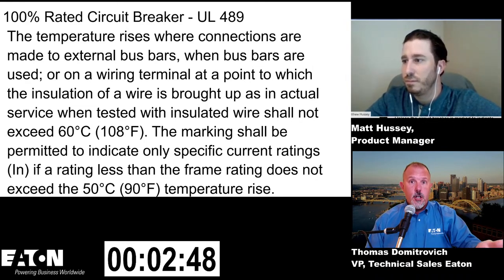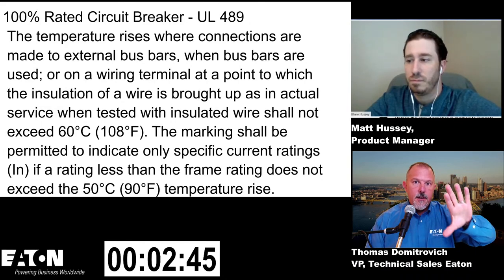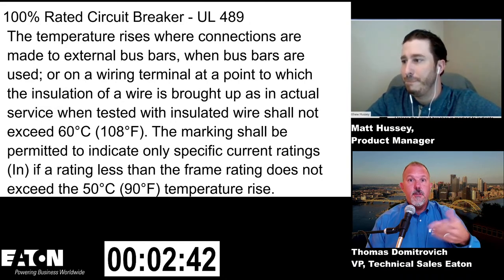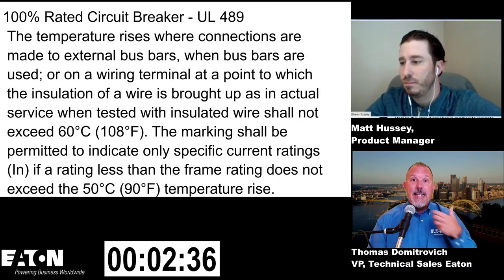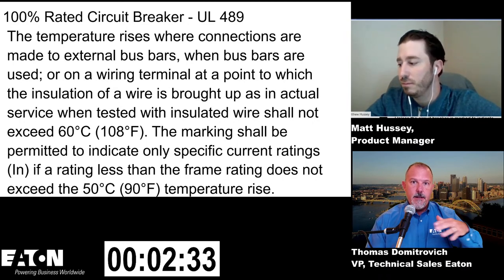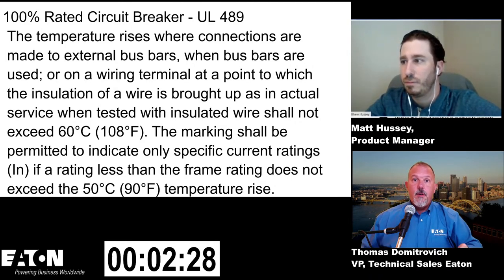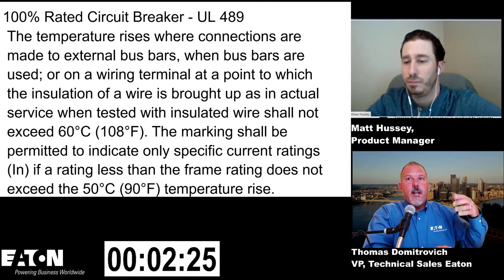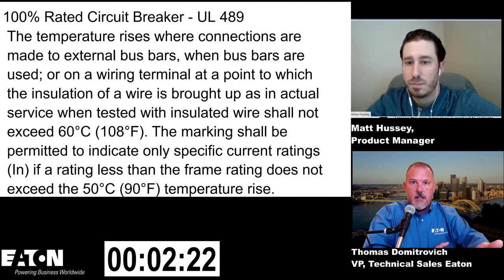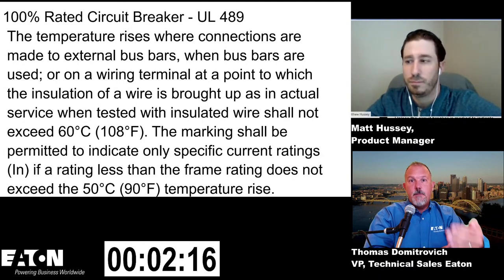So if it's a circuit breaker in an enclosure, I've got to worry about the lugs. I've got to worry about maybe the bus that's inside the enclosure, things like that. And I'm relying on the conductor size, the copper in that conductor, to help pull some of that heat out. And when I go with a 100% rated installation, I've taken my load calculation, I've not used the 1.25, I've calculated 100% times the continuous, 100% times the non-continuous. I've picked my conductor size based on that, which is going to be smaller. And now I'm going to land that on my circuit breaker or my fusible switch or whatnot.